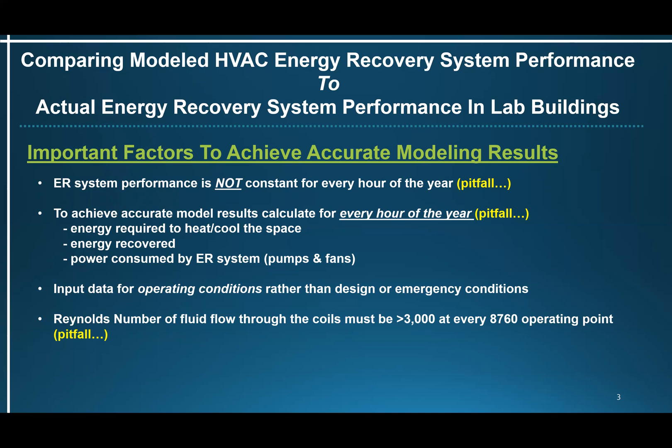Input data for operating conditions rather than design or emergency conditions. When modeling a system, the data input has to reflect the operating conditions for every hour of the year, not just the winter or summer or emergency design points. If the model input data is only for the winter design point, which only occurs say 10 hours a year, the model results will be far away from actual post-occupancy results.